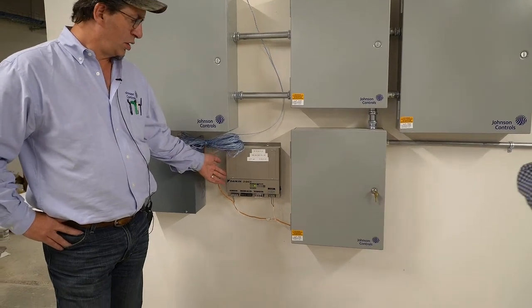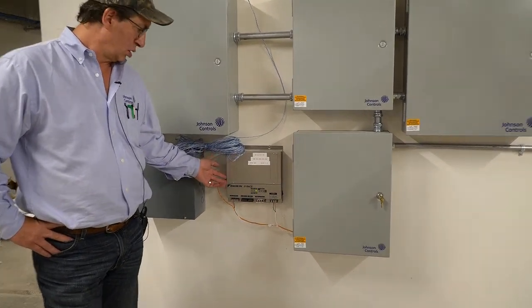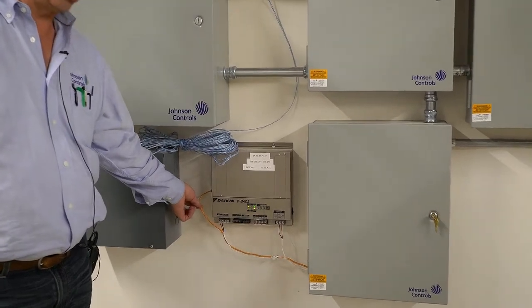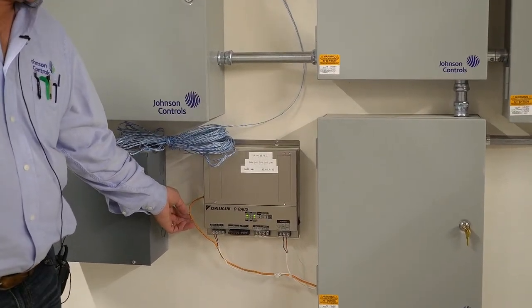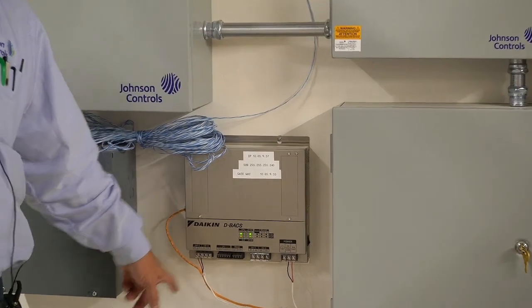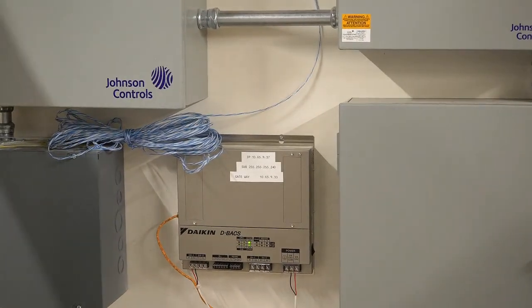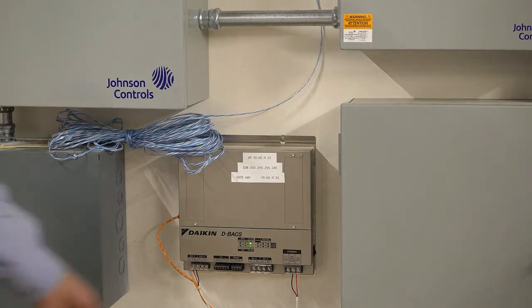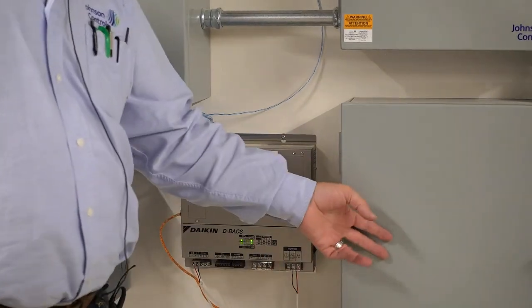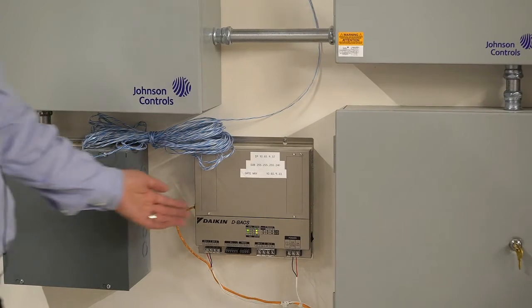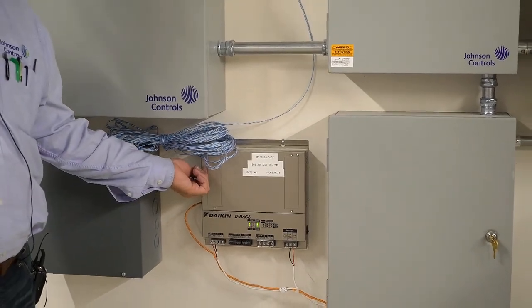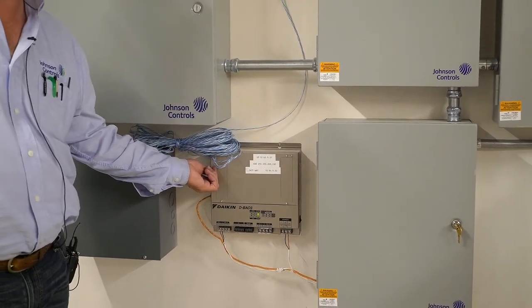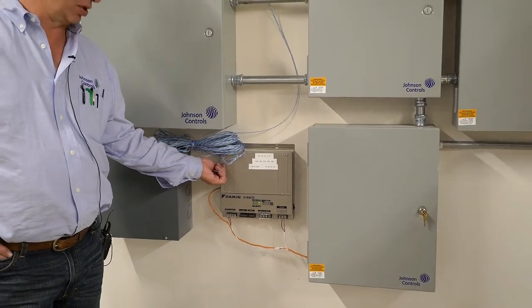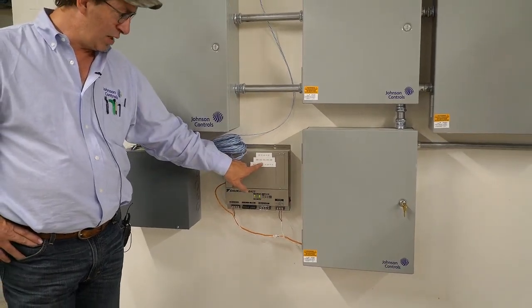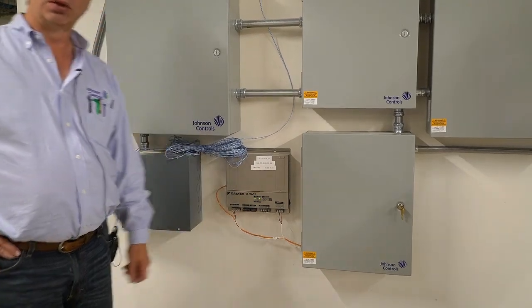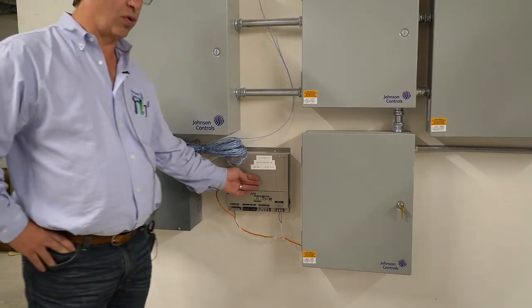So down here, this is the Daikin BACnet interface. This orange cable is the network cable from the IT department. This 2-wire goes all the way up to the 3rd unit on that balcony on the 2nd floor. And this is 24-volt power that comes out of this NAE panel. So this is how we're able to pull in points from the Daikin system into the front end of the Metasys system. This gives you the IP addresses, the subnet, and the gateway of the addressing that's been programmed in here.